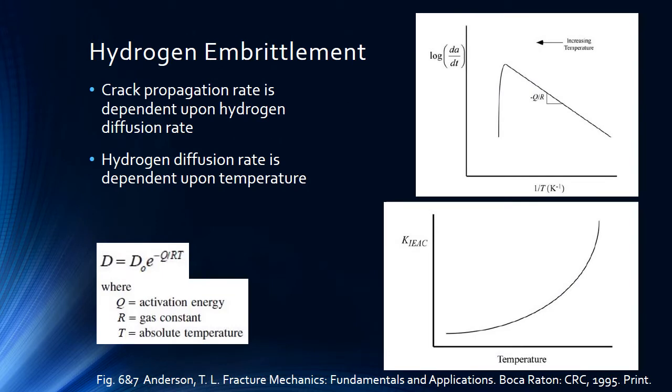For hydrogen embrittlement, the crack propagation rate is dependent upon the temperature. As the temperature increases, the diffusion rate also increases. You can see from the graph on the top right how the increase in temperature affects the crack growth rate. On the bottom right, you can see as the temperature increases, the critical stress intensity factor also increases.